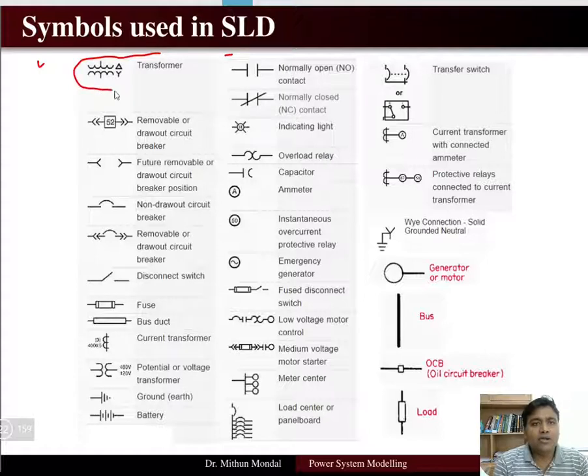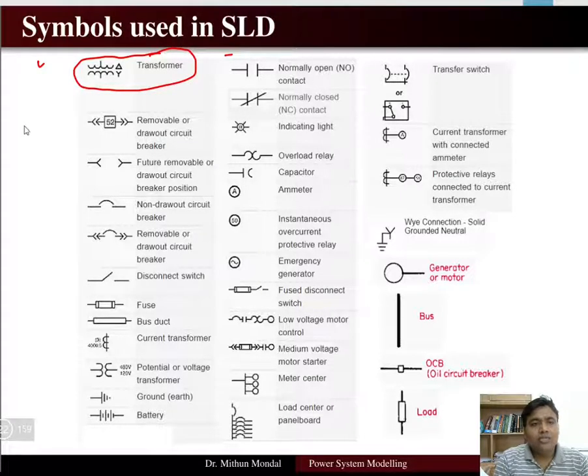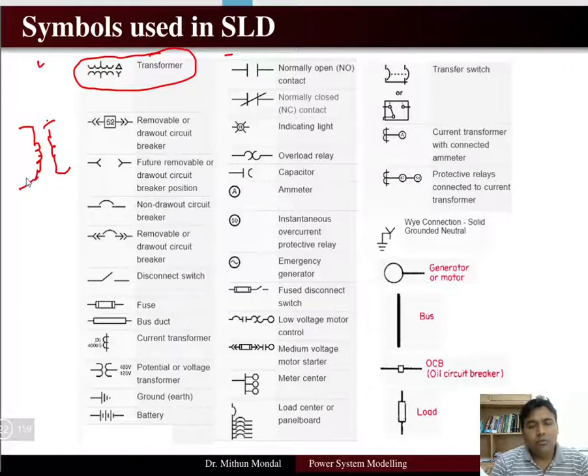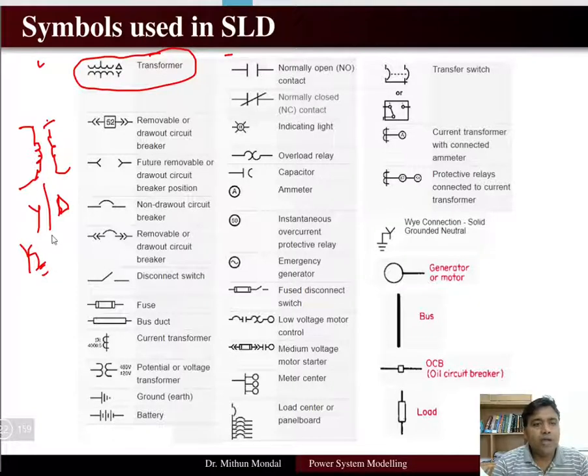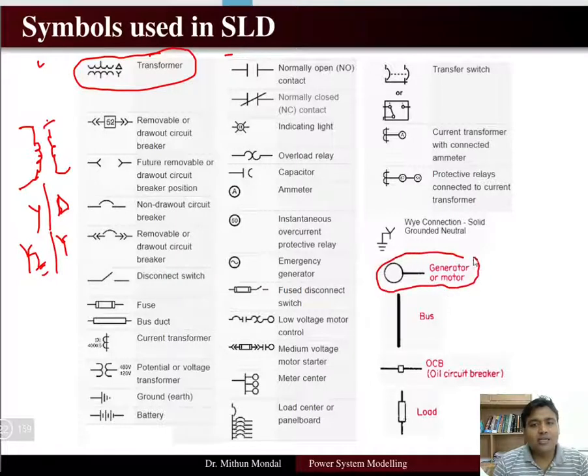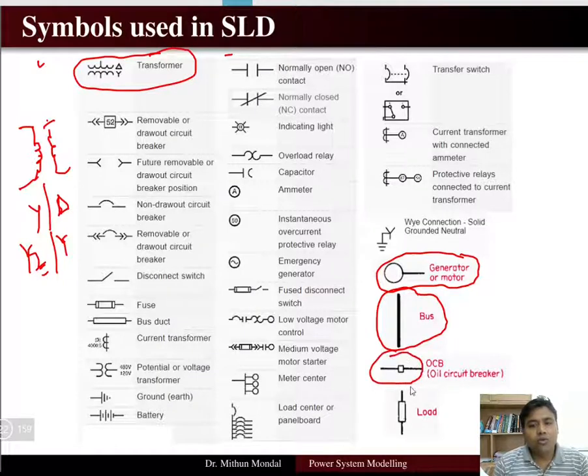The symbols used in a single line diagram include: a transformer represented by two inductors showing primary and secondary circuits, with star, delta, or grounded-star connections indicated. A generator or motor is represented by a circle with G or M written inside. The bus is represented by a thick horizontal or vertical line. A circuit breaker is represented by a small rectangle, and a load by a larger rectangle.